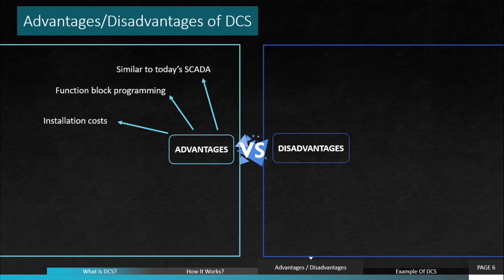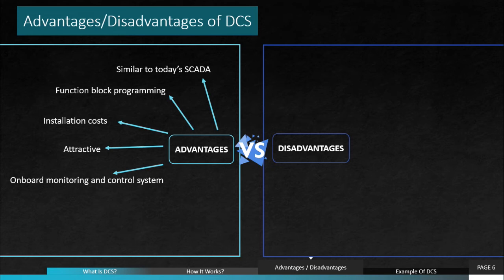This is because the autonomous controller can be located close in vicinity to the process, versus pulling long runs of I/O wire across a plant. It also reduces the installation cost by localizing control functions near the process plant with remote monitoring and supervision. DCS were attractive because the DCS manufacturer would supply both the local control level and central supervisory equipment as an integrated package, so that it can reduce the risk of design integration. Also, DCS has an onboard monitoring and control system so that it will save development time.